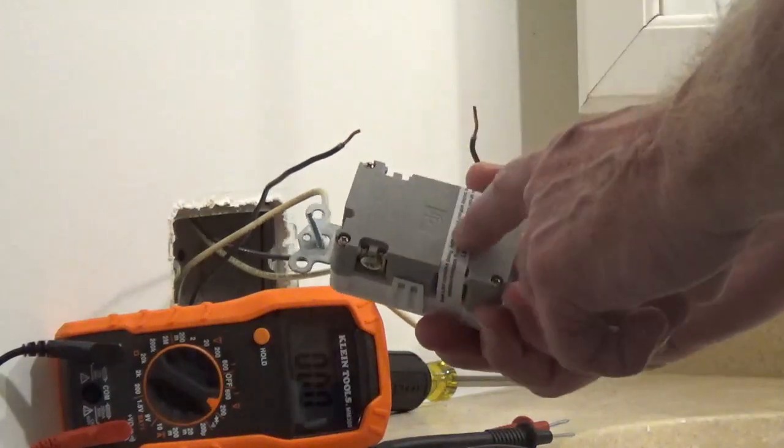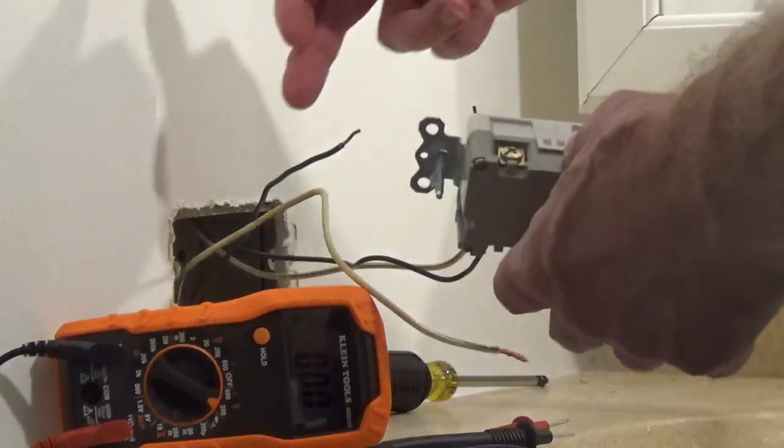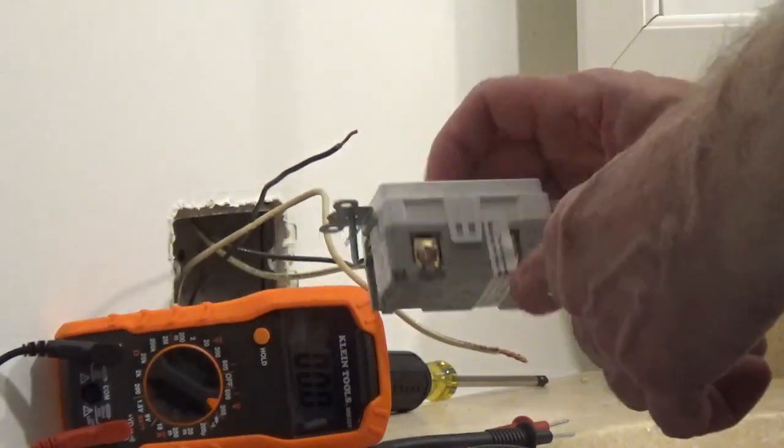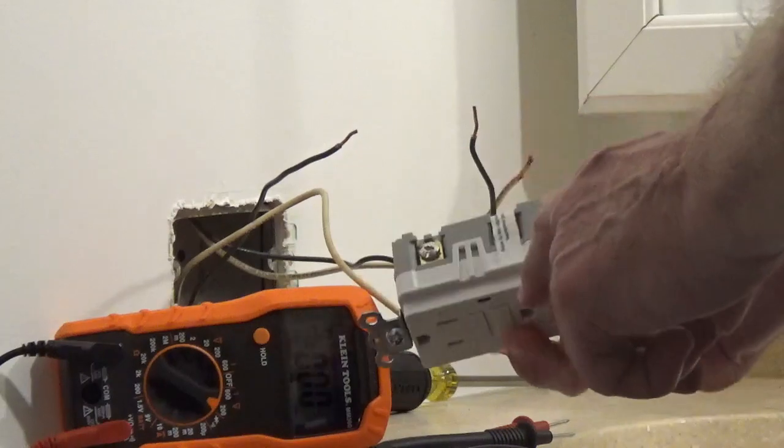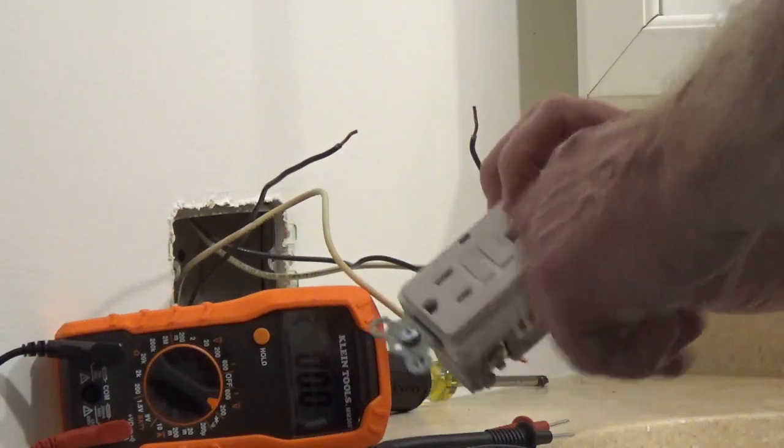And that's the side without the tape generally, and you'll be using the hot wire, in this case, the black wire to the brass side or the narrow slot, and your white neutral wire to the silver screw or the wide slot.